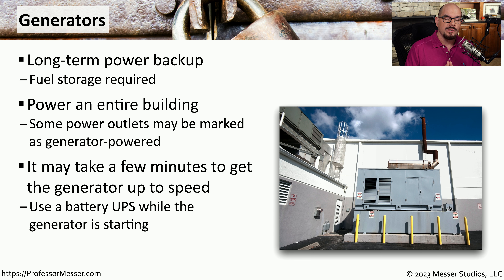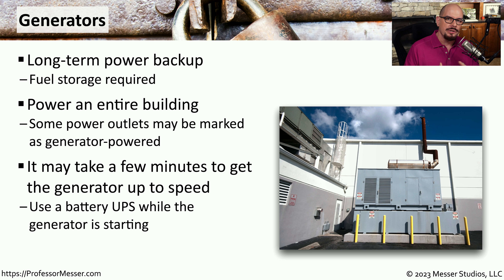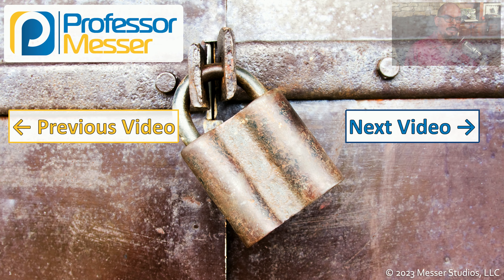Most organizations take advantage of both types of power backup — both the UPS and the generator. This is because a power outage causes the generator to turn on, but there's a ramp-up process while the generator is starting up, during which you may be without power for about a minute. You can use your UPS to cover that time frame when the generator is not yet running, and then once the generator provides power to the building, everything can move over to generator power.